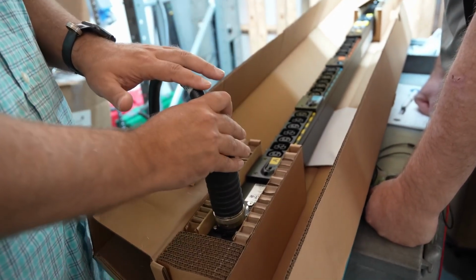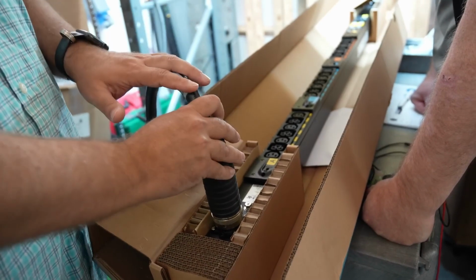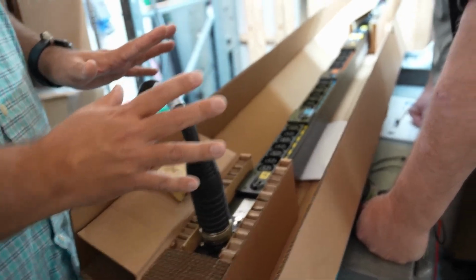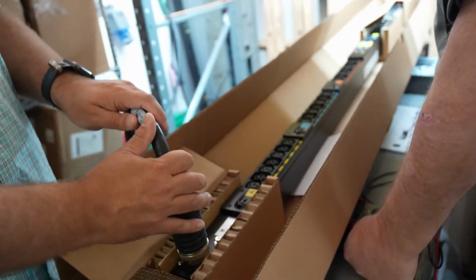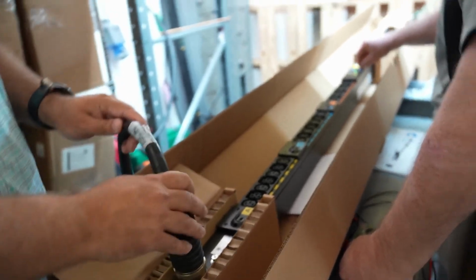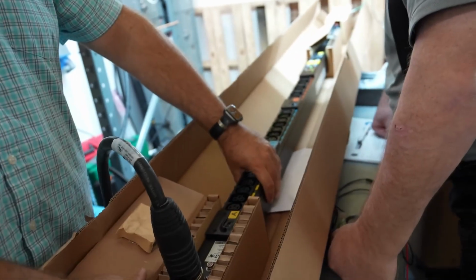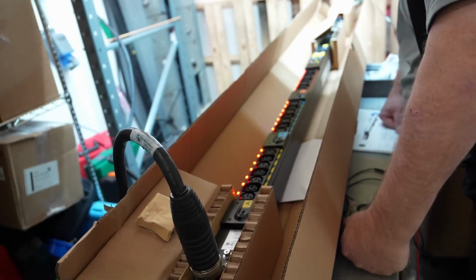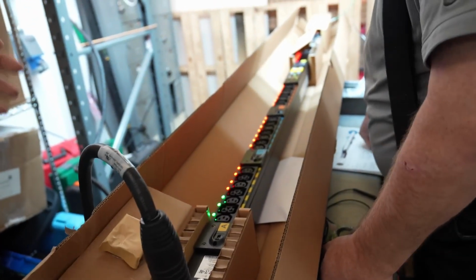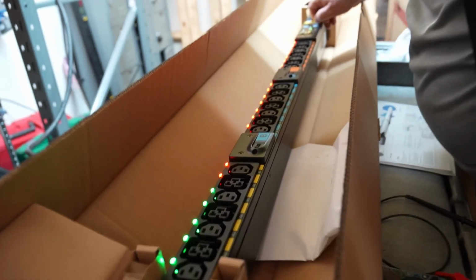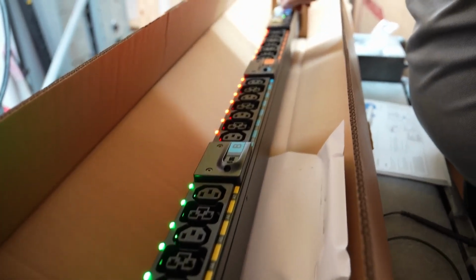So this thing can be a 20 amp, 208 volt single phase power distribution unit that can handle about 3 kilowatts of power, or I change the cable out and it can be a monster that handles 17 kilowatts of power, all without having to change out the chassis. Very cool. We'll show you later why not having to change out the PDU is so important, because these things get buried inside the cabinet.